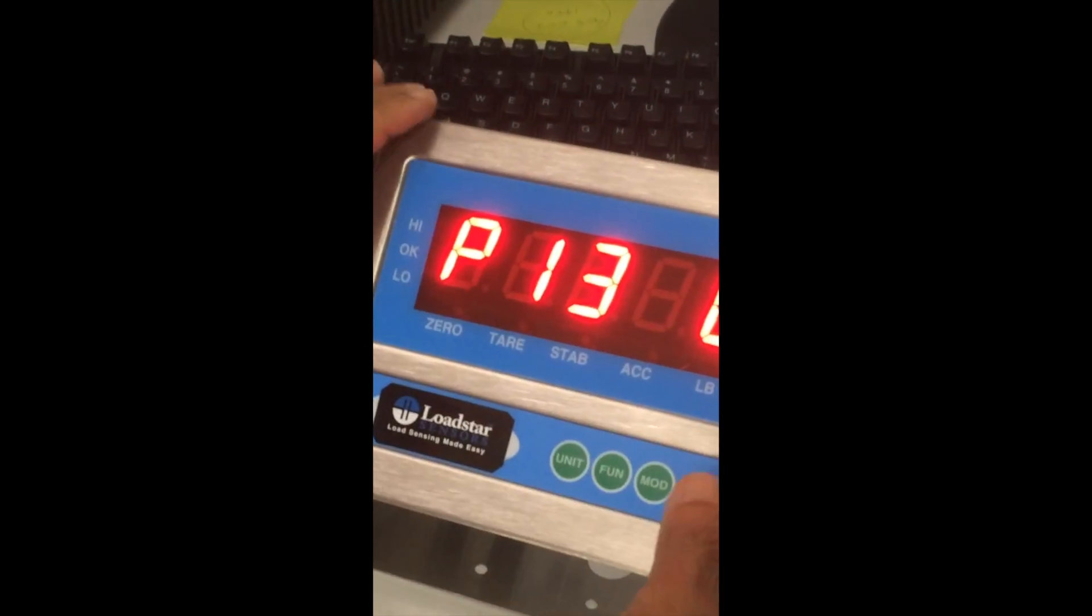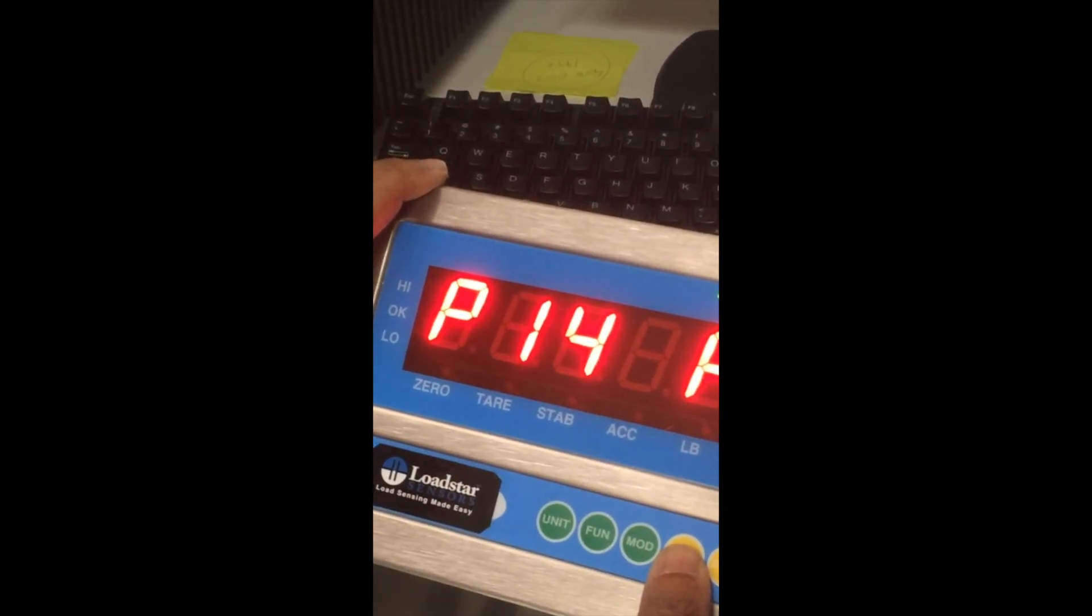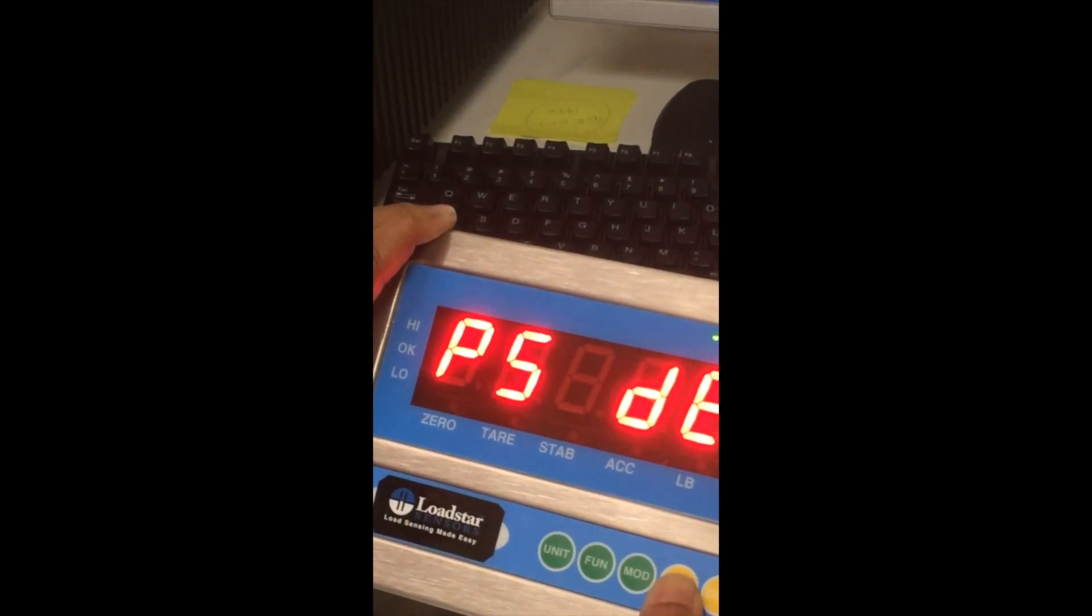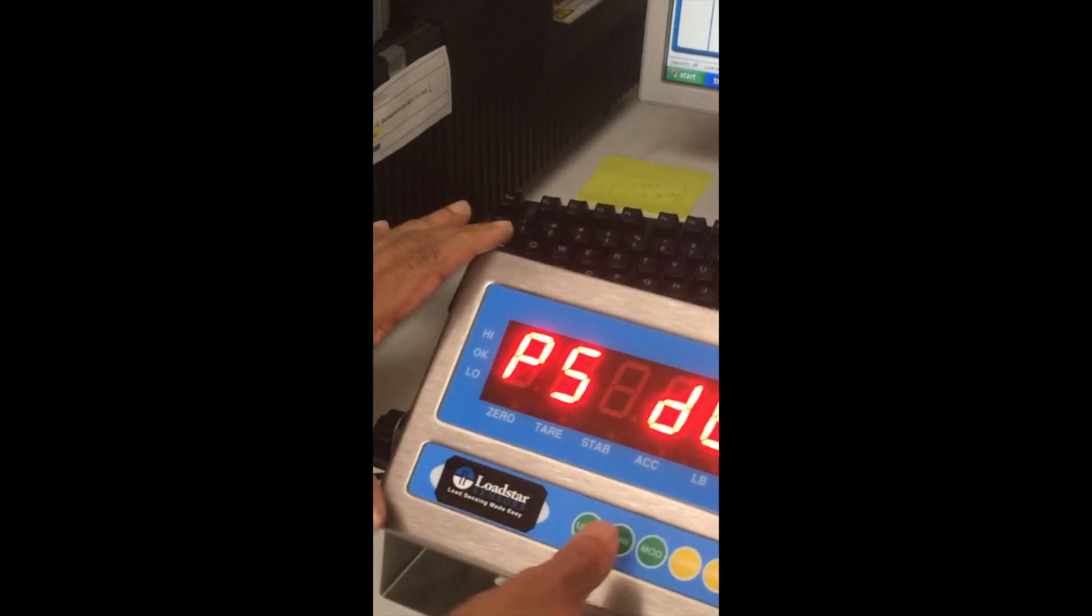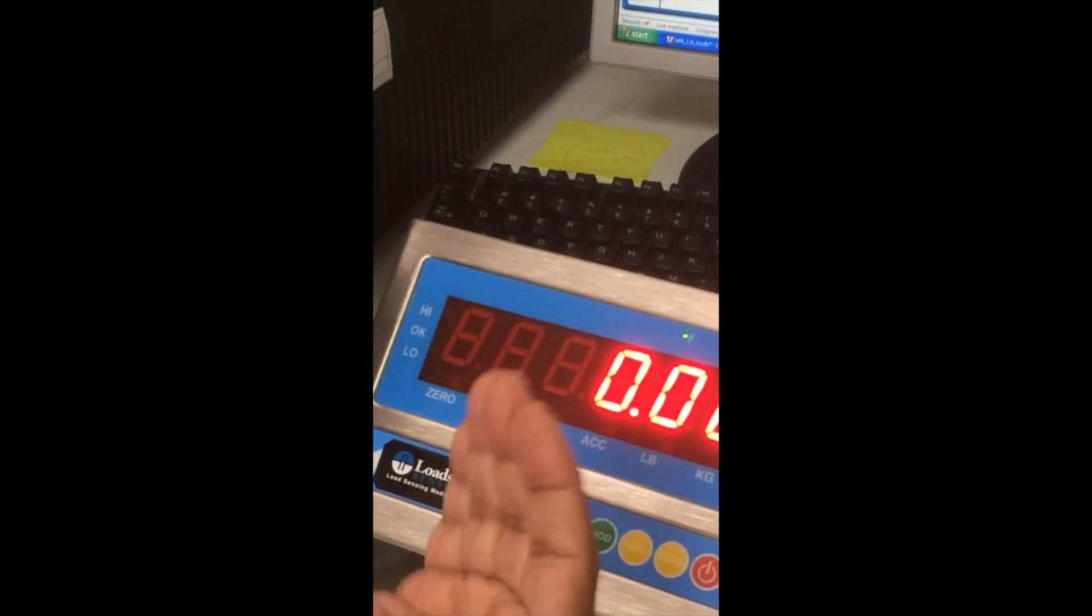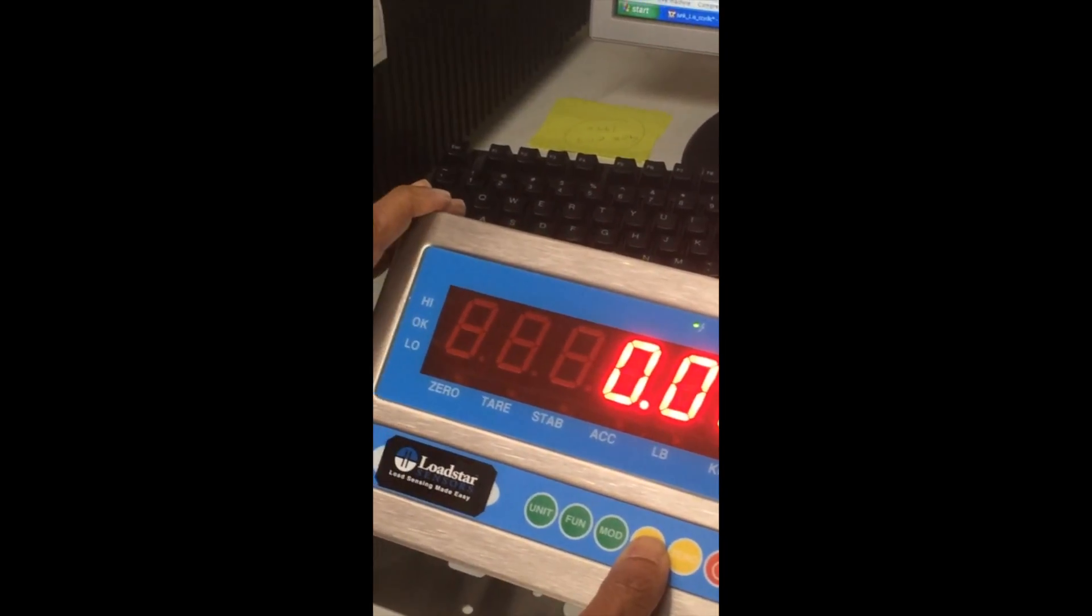Now we go to other setup parameters. So we go to P5. That's the number of decimals you want in the display. So press the function key. Default is set to two decimals to display. You can use the tare key to adjust it. Now we are happy with two. We will accept it. Press function.